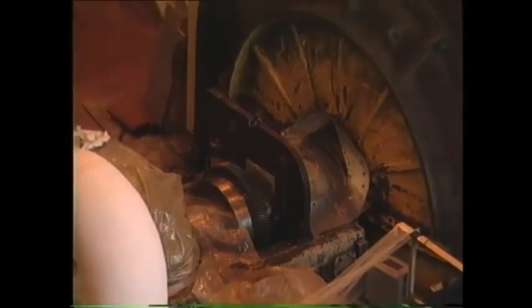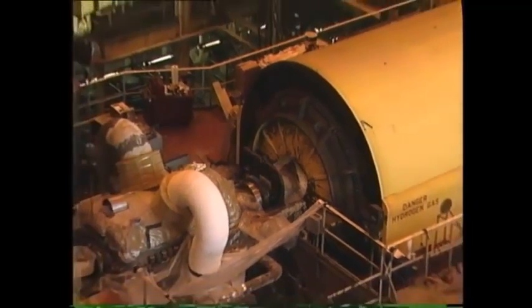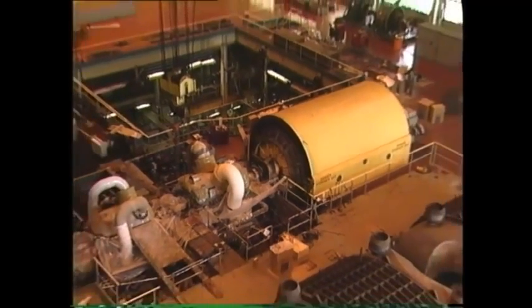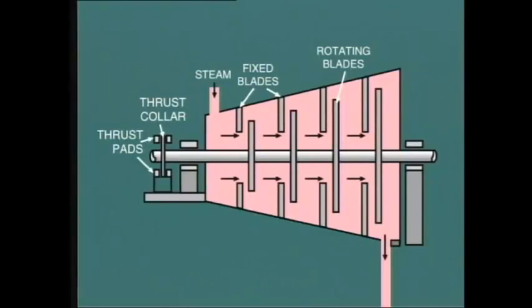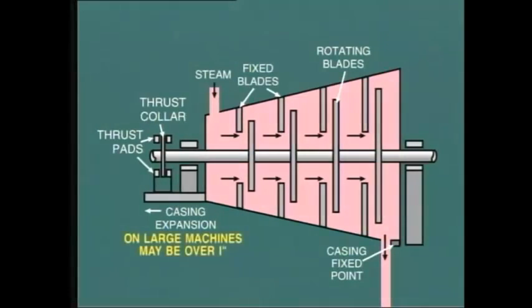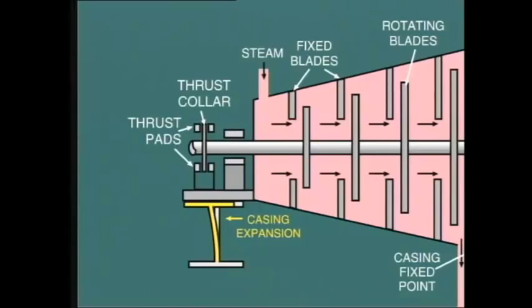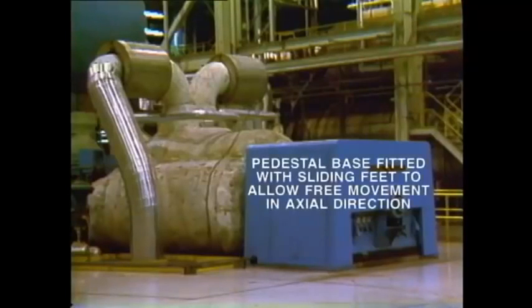During construction and maintenance of the machine, these pads are carefully set to ensure that the correct clearances exist between rotating and stationary parts. Allowance must be made for the casing to expand as it becomes heated by the steam flow. In a single-cylinder machine like this, the normal method is to anchor the machine solidly at the low-pressure end, that is, at the turbine exhaust, and allow the front end pedestal to move forwards. In large machines, the expansion in this longitudinal direction may be over 1 inch, that is, 25 millimeters. In this particular machine, the pedestal is fixed to a flexible support which allows the movement to take place. A more common arrangement on larger machines is to fit the base of the pedestal with sliding feet to allow free movement in the axial direction.